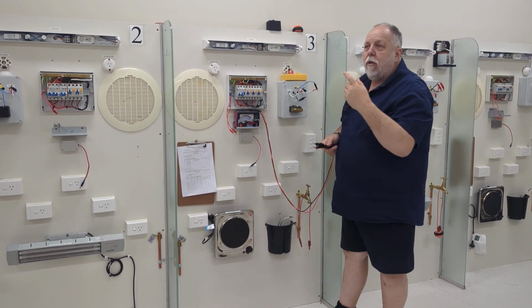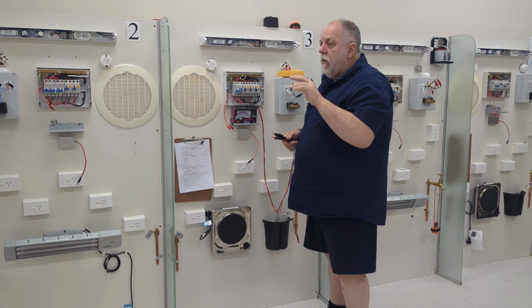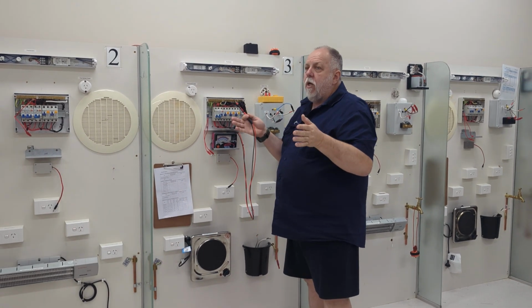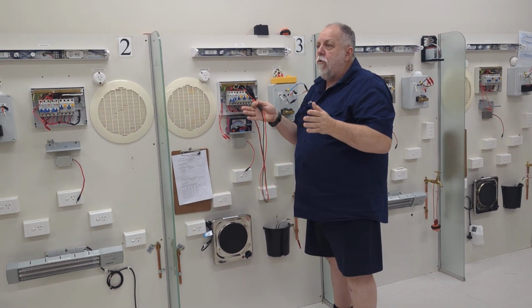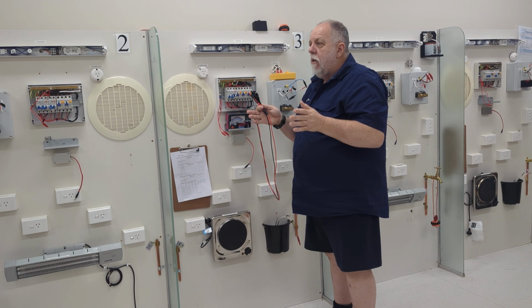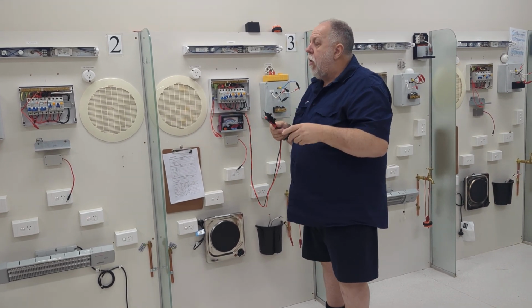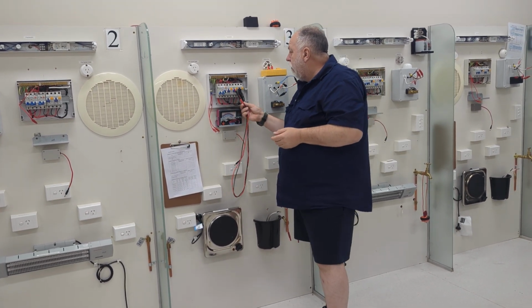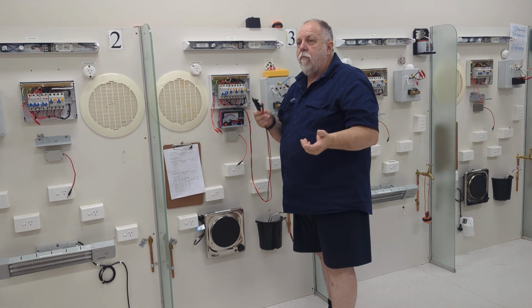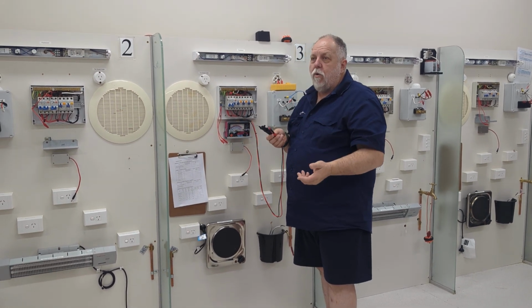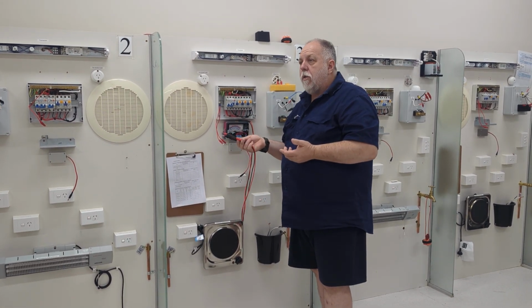Yes, we can start going back to an individual value. The thing with an RCD is you isolate pretty much the active and the neutral separately. Do you understand what I'm getting at? Unless you want to put a bridge. Sometimes when you're going across and testing, you can have a good active but a crook neutral, or the active's crook and the neutral's okay. Do you understand what I'm getting at?